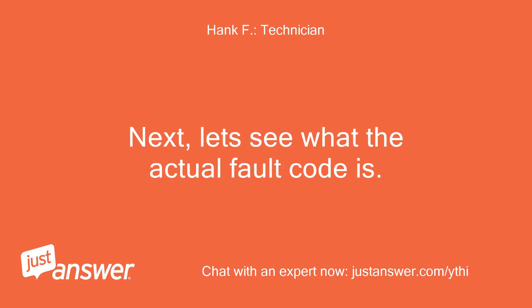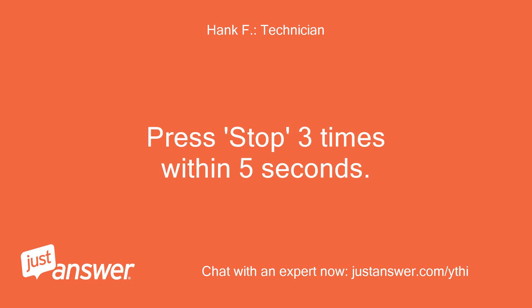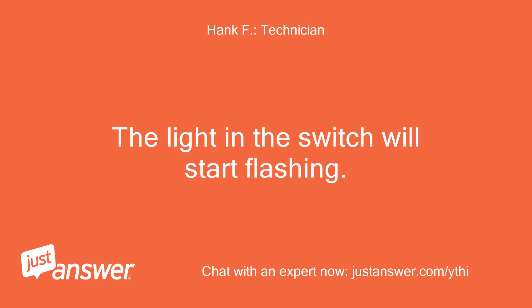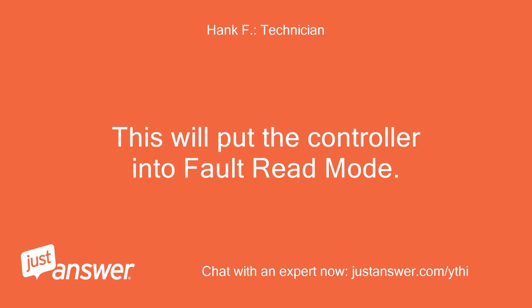Next, let's see what the actual fault code is. Go to the genset and use the switch on the set itself. Press stop 3 times within 5 seconds. The light in the switch will start flashing. If the light flashes 3 times, pauses for 3 seconds, and flashes 3 more times, press and immediately release stop 1 more time. This will put the controller in Fault Read Mode.